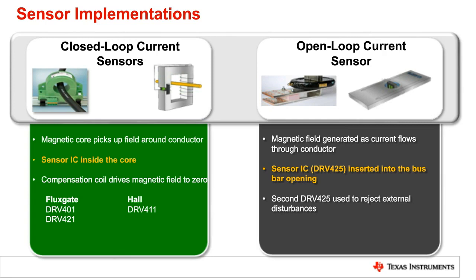Typically inside these closed loop sensors, it's going to be a module type solution where a toroid will concentrate the field around the conductor. The sensor will actually be integrated into this module itself, so the output will be a simple analog voltage that you can read. Let's look a little closer at how those are designed and implemented.